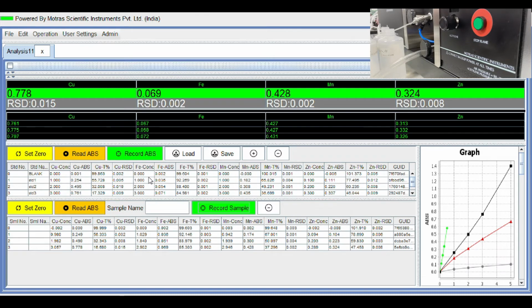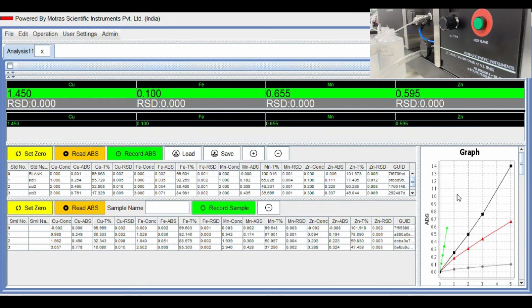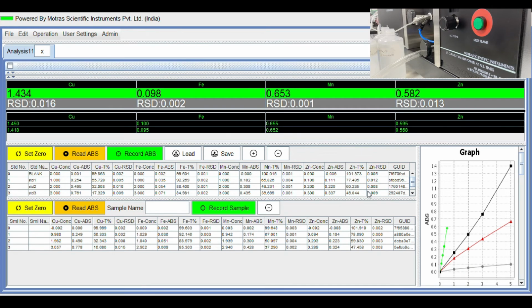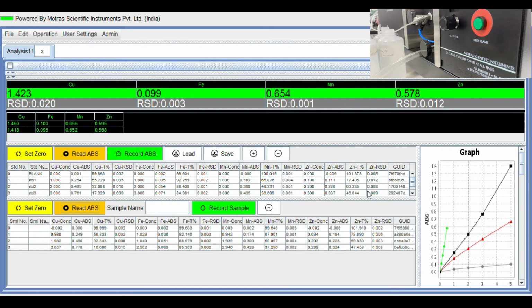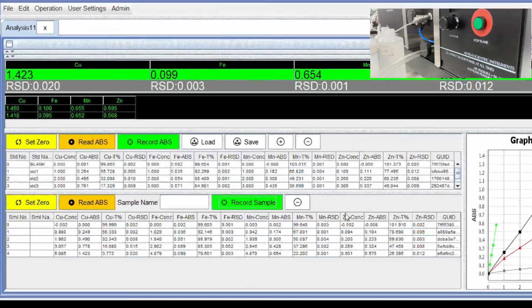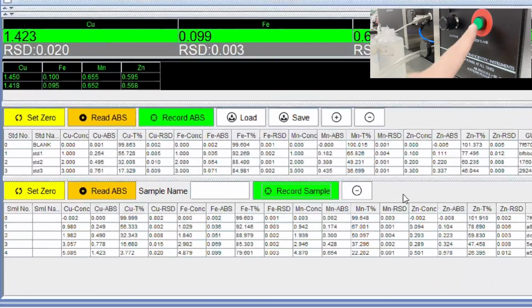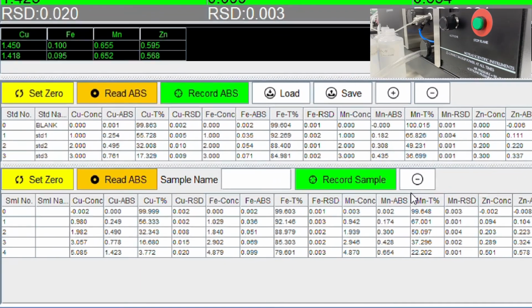Now we'll run the 5 ppm standard as a sample. Again, we see that the repeatability is very good even at this scale of ABS. We'll go ahead and record it. All the concentrations are reported as exact.